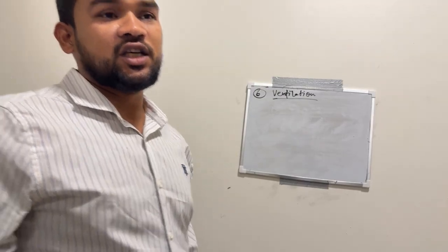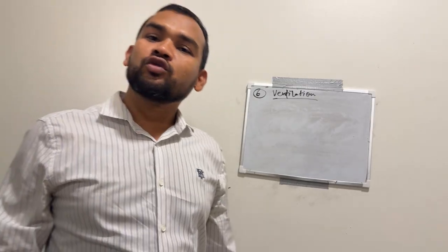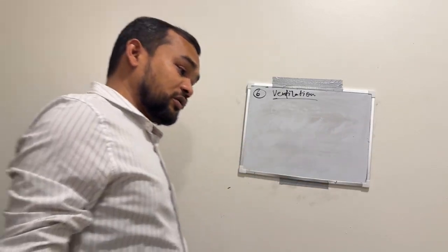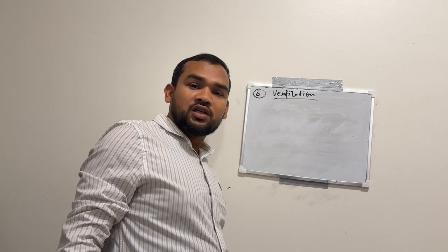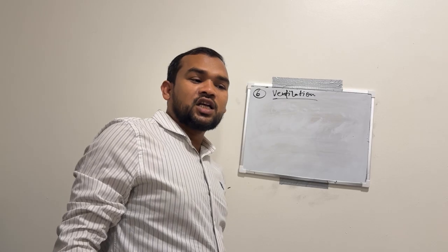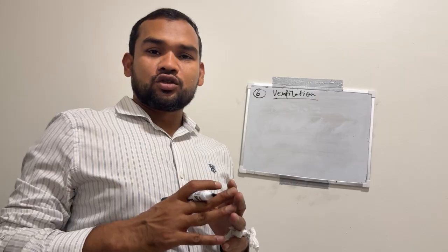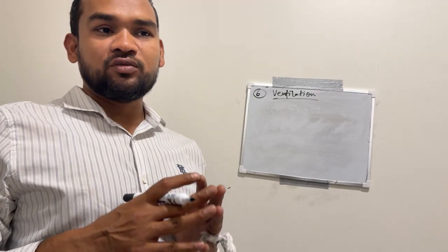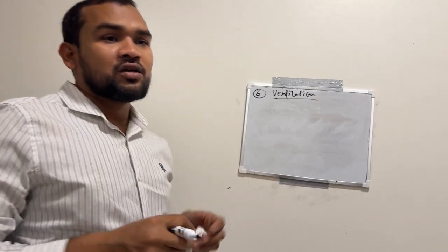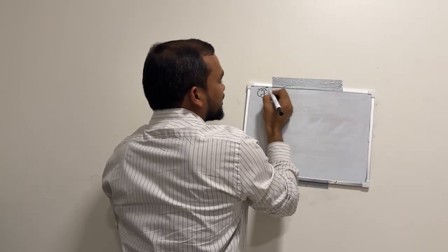So we will check. Ventilation, like an HVAC system, can dilute or temporarily delay smoke particles from reaching the detectors. So what we will do in this case is install the smoke detector at least 36 inches from the diffuser, and the HVAC system shall be shut down in case of any fire, so it will stop the spread of smoke or fire. Detectors shall be installed in the return air duct. This is called ventilation. Our next topic is number 7, smoke stratification.